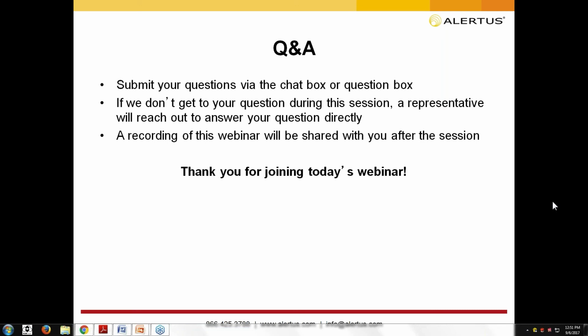So hopefully, if you have a mass notification system where the risk analysis dictates that the mass notification should take precedence, then the mass notification system will actually deactivate that fire alarm if it happens to be going on, or just stop it from going off if the mass notification system is already going off, and prevent that type of scenario. Yeah, definitely.